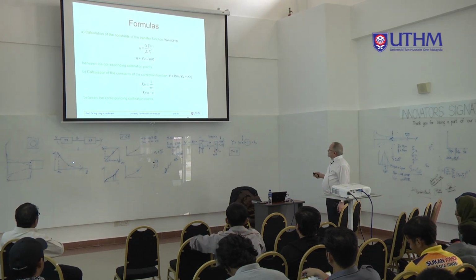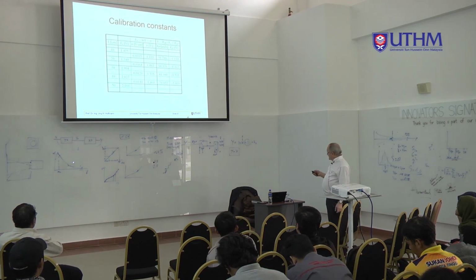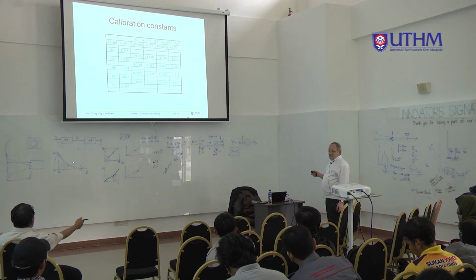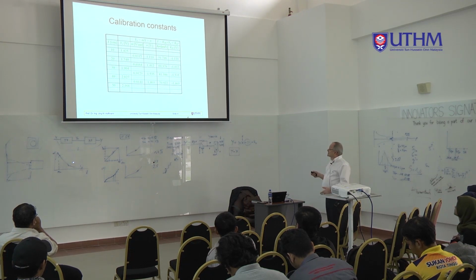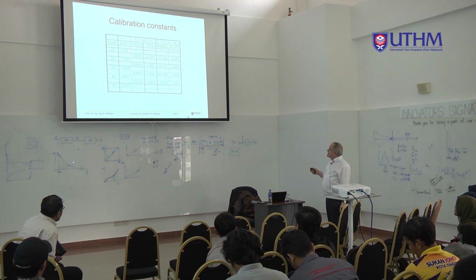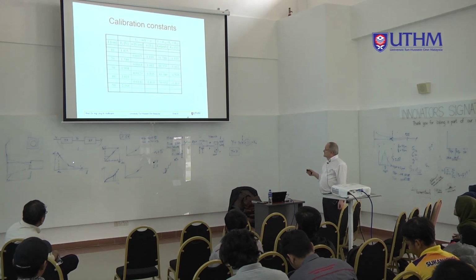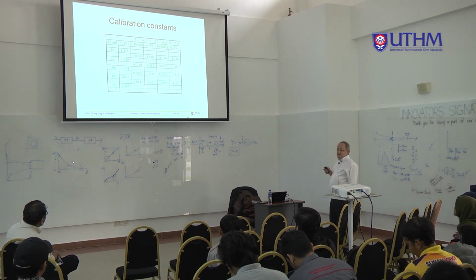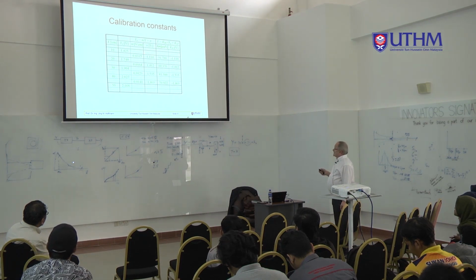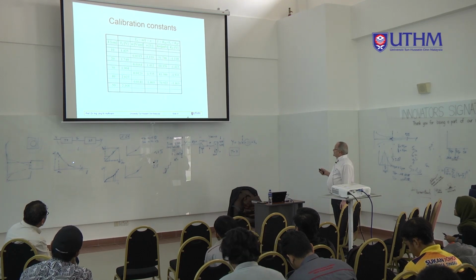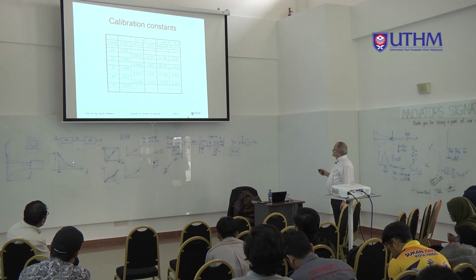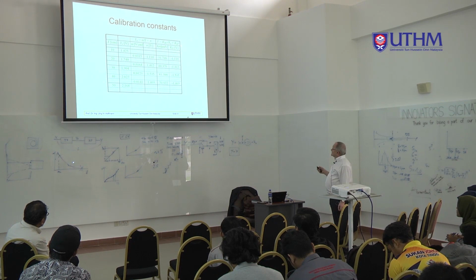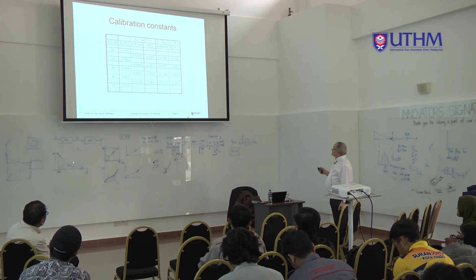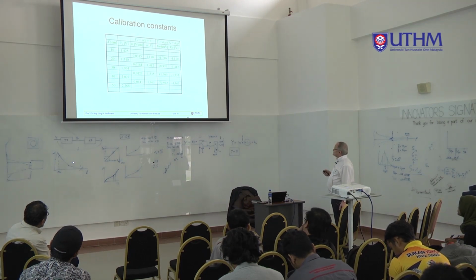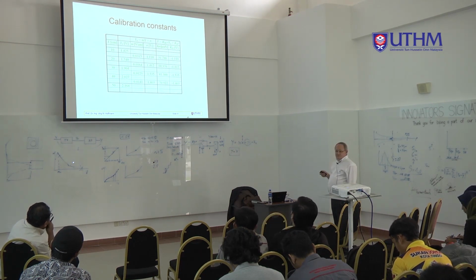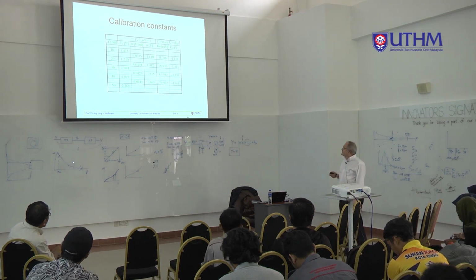So that we can set up, that is a mathematics, but I show you that later again, that you can set up this table. Exactly the same as we have had it in the first example. It's exactly the same principle. You have 10 centimeter, and that is a mean from all measurement values at 10 centimeters. This is a mean of all measurement values at 20 centimeter. You have to calculate the m, you have to calculate the n, you have to calculate the km. Km is 1 divided by m, and kn is minus n. You see here the correction function, the calibration function, and here you see the transfer function. You see also the constants have all units, and if you calculate with the units, you should also get the unit in the end.